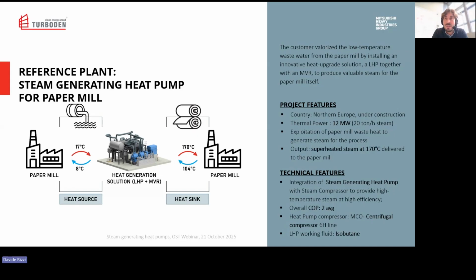Those are the averages - in summer it could be a bit higher and in winter a bit lower, whereas the needs of the process are 170 degrees C, meaning 3 bar steam superheated with a return temperature of 100 degrees C. So the system is sized for 12 megawatt thermal power, meaning around 20 tons of steam per hour of superheated steam delivered directly to the paper process. The system is composed of two steps.